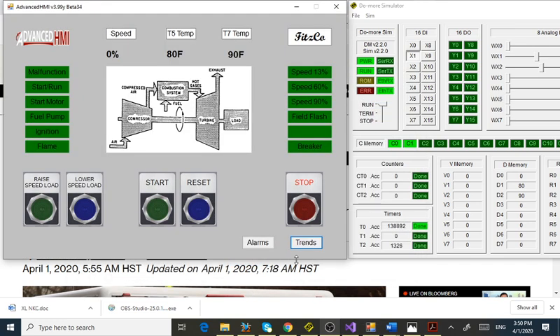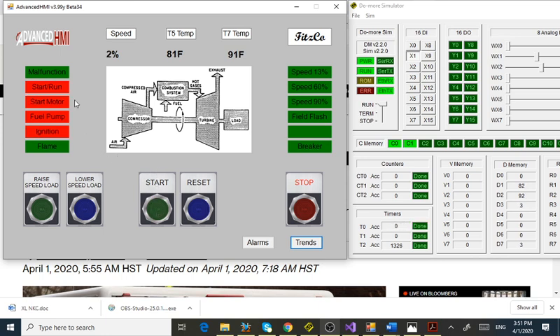Let's go back to the main page and start this unit to see how it would operate. In my simulation software I put three ramps for the analog signals — speed, T5 temp, and T7 — to roughly mimic a startup. When malfunctions are cleared, it's ready to start. When I hit start, my speed starts coming up because my start relay held.